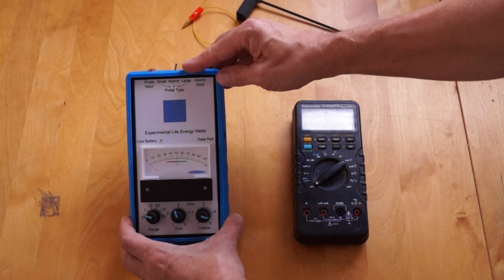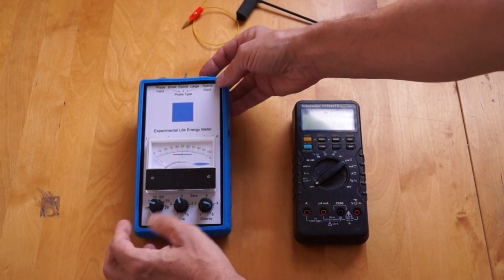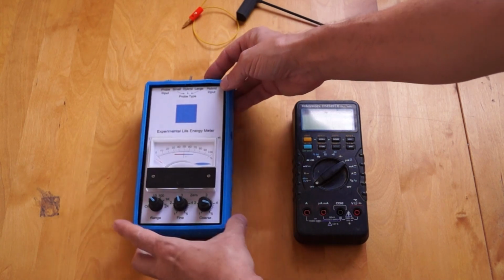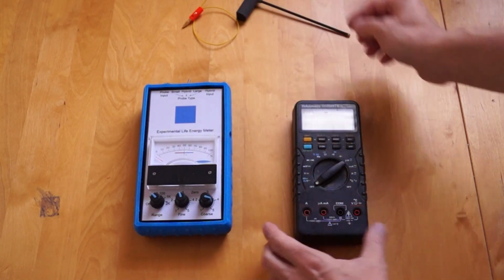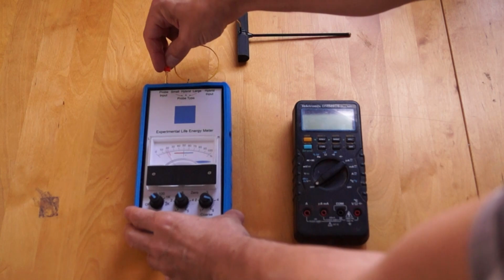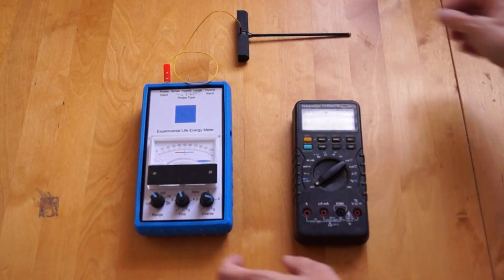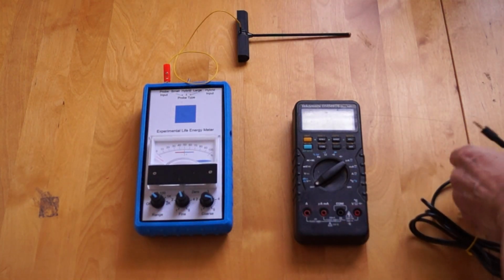On the LM4 Life Energy Meter, set the external probe switch to the large setting. Now set the range to ×1. Insert the red earth probe jack into the external probe fitting on the LM4.